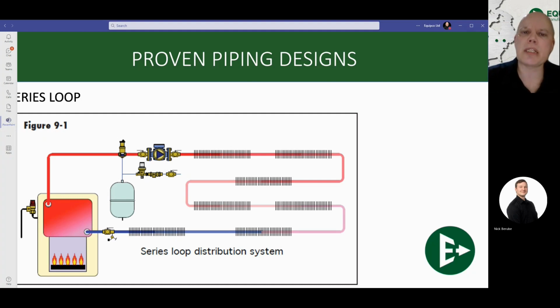Okay, so this number one proven piping design is called a series loop, where essentially we're coming out of the boiler with a good hot temperature of like 180 degrees, hitting our circulator, and then we go into the first rad, and then continue on in series into each additional rad or heat emitter, whatever it is going to be. Now, one thing you will notice is the color changing from dark red into pink and then into blue, meaning that as each rad is giving off its heat, the temperature of the loop is getting colder and colder.